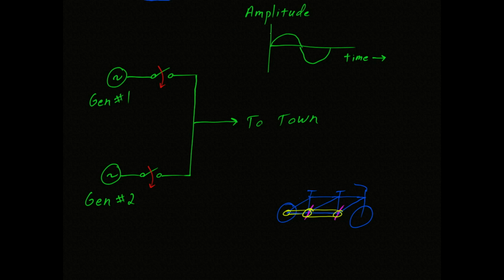We talked about this amplitude up here, and we said that each generator by itself produces a sinusoid. Well, as soon as you close these 2 circuit breakers, the output of generator 1 is felt by generator 2, and vice versa. In fact, everywhere along this point is the same voltage, so the generators must be turning in lockstep with each other, again like Alice and Bob on the bicycle. And if all is working as it should, each generator is providing an equal amount of power to the town.